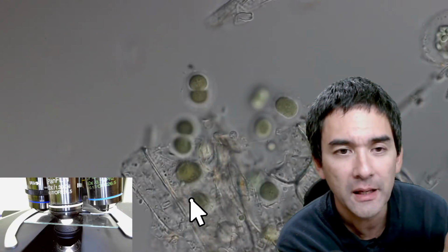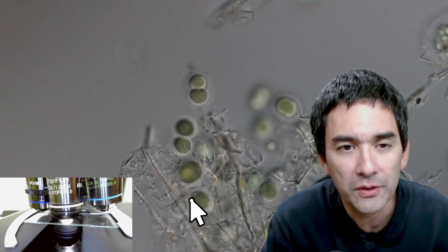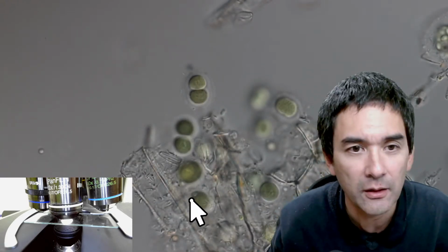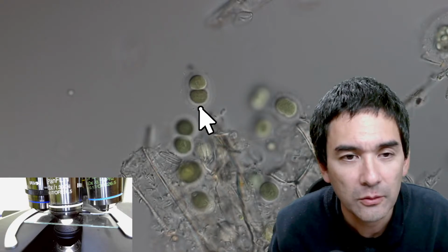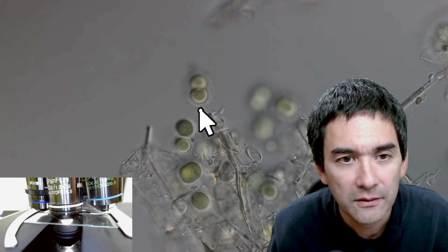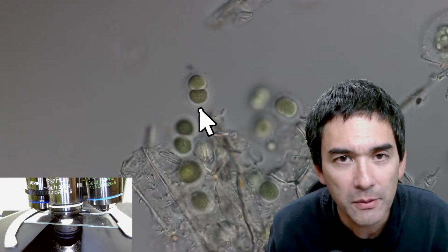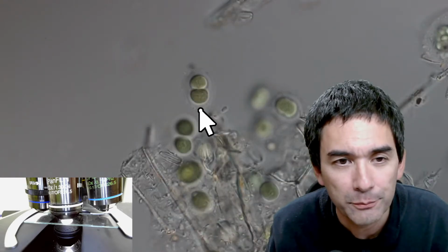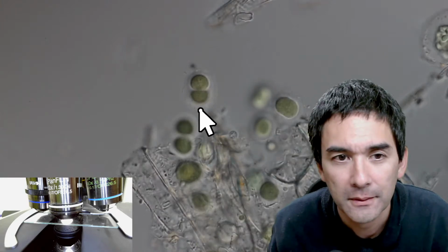Something that I also sometimes notice is the following: that when you move, then the focus or, for example, look at this guy over here. Okay, look when I focus. Yeah, do you actually see it move? And the reason why it moves is because of the oil, and so there is a very tiny amount of pressure being applied on the cover glass.